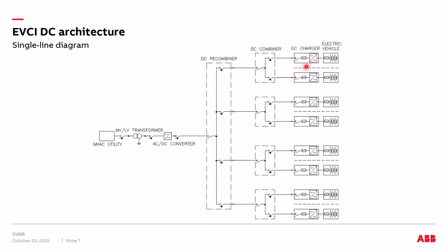Then we have in series a switching device, usually a switch, to be able to disconnect the circuit also in so-called load condition, so with current, in series with a protective device, also in this case usually an internal fuse. Then, in order to connect these DC chargers in parallel, we can have one or more DC combiners, and in a very large scale DC infrastructure, we can have also the so-called DC recombiners, like for example we have in large DC photovoltaic plants. And then we have one or more main AC-DC converters.